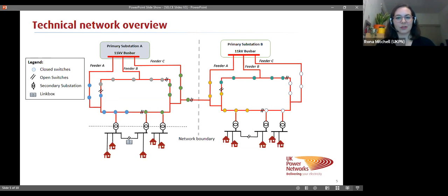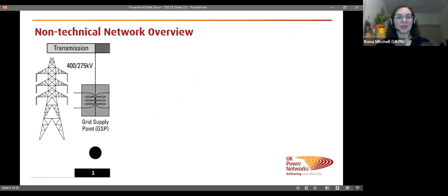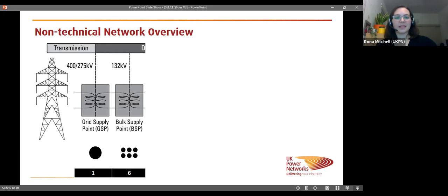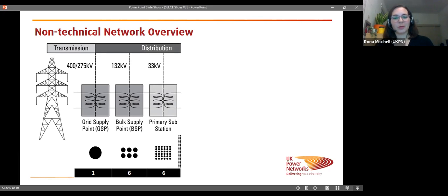A slightly less technical network overview is to start from the highest level of voltage, which is the transmission network, looked after by National Grid - they have their big towers. With lockdown you're probably not doing as many journeys and travels, but you quite often see the big towers along the motorways. For every grid supply point, they would then step down to a slightly lower voltage, but still very high, called a bulk supply point. One grid supply point would feed 6 bulk supply points, and then this is into what the distribution network looks after.